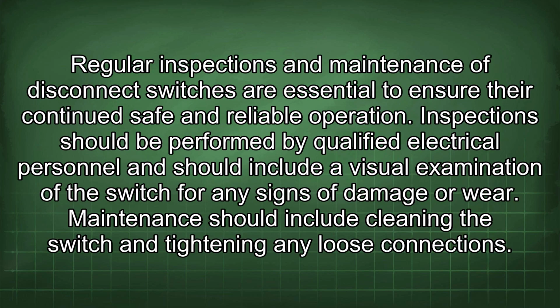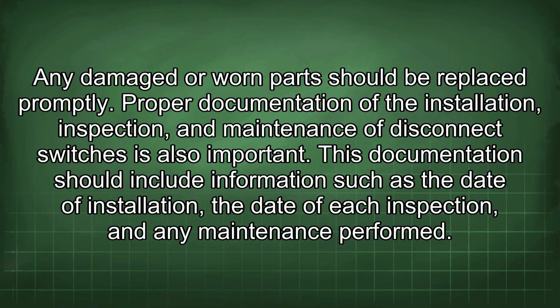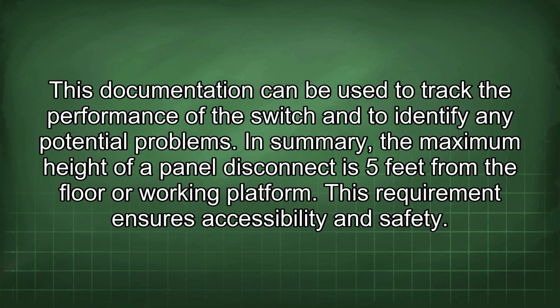Regular inspections and maintenance of disconnect switches are essential to ensure their continued safe and reliable operation. Inspections should be performed by qualified electrical personnel and should include a visual examination of the switch for any signs of damage or wear. Maintenance should include cleaning the switch and tightening any loose connections. Any damaged or worn part should be replaced promptly. Proper documentation of the installation, inspection, and maintenance of disconnect switches is also important. This documentation should include information such as the date of installation, the date of each inspection, and any maintenance performed. This documentation can be used to track the performance of the switch and to identify any potential problems.